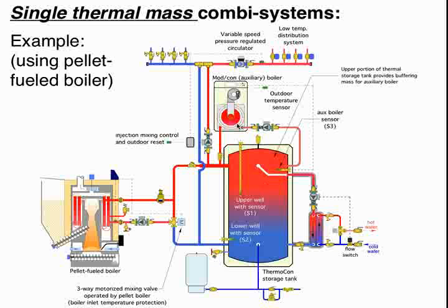And then you recognize that if you just kind of cover up this, I'll talk about that in a minute. This is a two-pipe buffer tank. This could be a thermocon tank set up. We've got an auxiliary boiler tied in just into the upper portion of the tank. So the auxiliary boiler can basically heat this upper portion of the tank. And we've got zoning going on. Now, I'm showing 4 zones, but maybe we have 8 zones here. Let's say we have a lot of zoning going on.